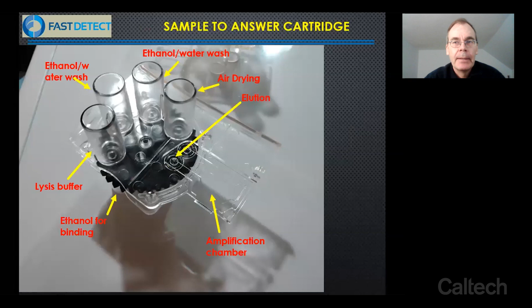We have preloaded cartridges which have all the chemistry on board, and all we need to do is add the patient sample and basically put it into the system. We have lyophilized reagents that now give us a good shelf life. And when we heat and cool the sample, we do it by cold finger cooling. Instead of using a refrigeration system, we have just a cold metal hitting the bottom of the sample to cool it down from 95 degrees to 55 degrees.